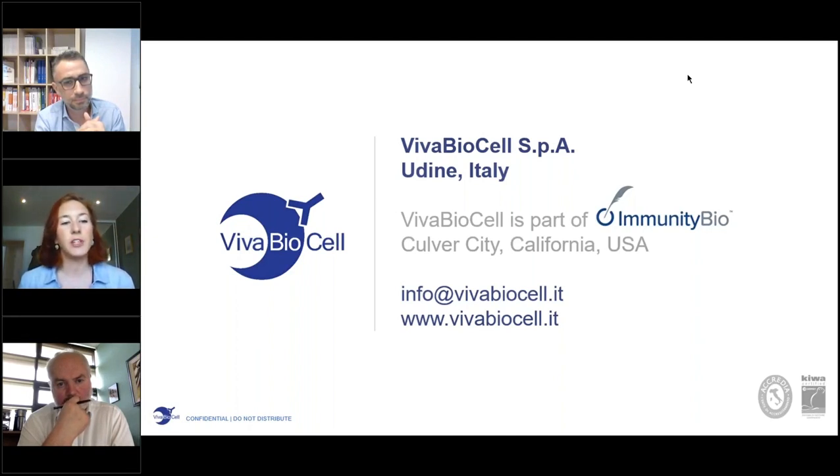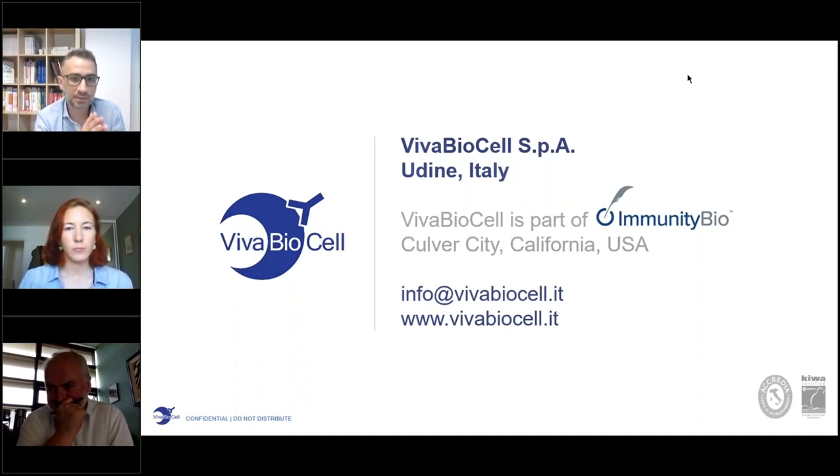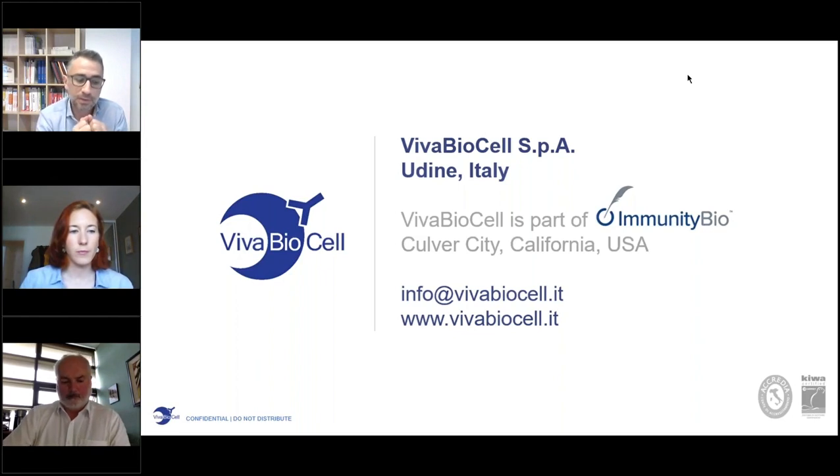Maximilian Otterson asked if it's possible to use carriers in the system for culture of suspension-adapted cells. We have never tried that kind of application — the applications we are familiar with are based on cells in adhesion or cells in suspension, but without the use of carriers, though this is something that may be discussed. Jorge Blanco asked if it's possible to take culture samples to analyze metabolites. Yes, this is possible — the disposable cartridges are equipped with sampling ports with one-way valves that allow sampling while keeping sterility without opening the circuit, so you can sample during expansion even in a grade D environment without risk of contamination.